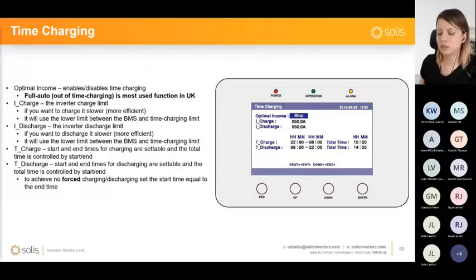This is not related to the self-use mode. This is just when, for example, the customer has a lower tariff during nighttime. Then here you would set a time charging from, here's just, 22 to 8 o'clock in the morning. It's going to show you that you have 10 hours of charging from the grid with a maximum current for charging of 50 amps. But the battery management system will decide on the exact value used for charging. But this is just a limit that you can set on the inverter.